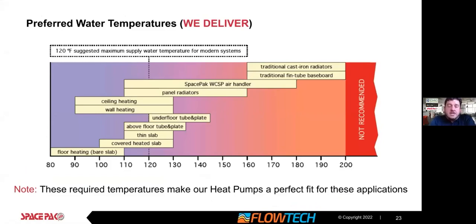The sweet spot for radiant hydronic is SpacePak. The SpacePak sweet spot is between 100 and 125 degree water temperature. And it just so happens, luckily, that that's very common to a great application for many of the distribution methods that we see in hydronics, all the way from radiant floor heating to underfloor, wall and ceiling radiant panels, radiators, SpacePak or conventional air handlers. All of those methods will be well suited to be paired up with a SpacePak unit. So they're applicable to a wide variety of existing and new construction techniques. What is not a good fit are high temp applications, so high temp cast radiators or baseboard.